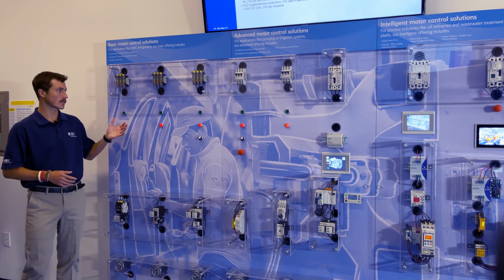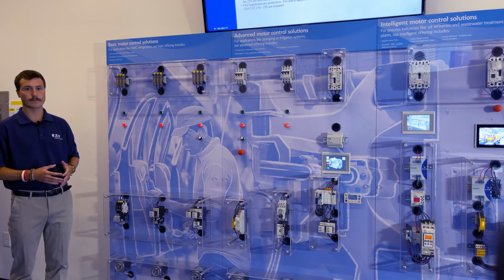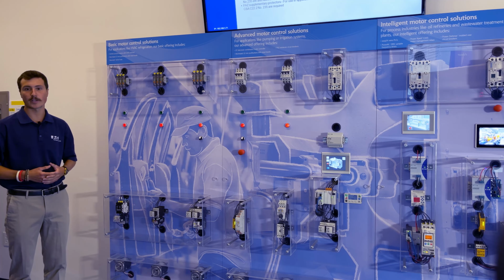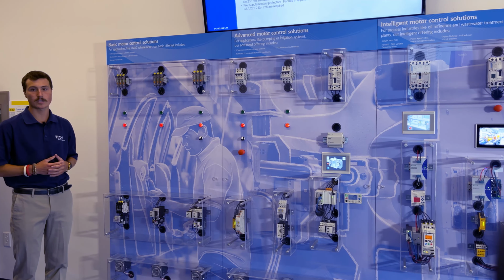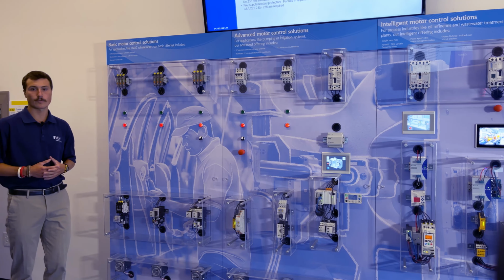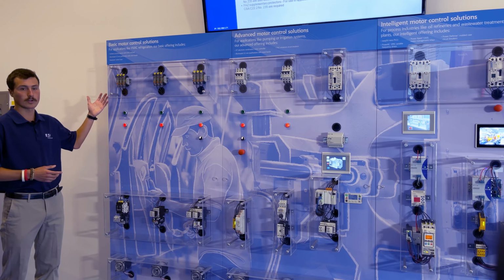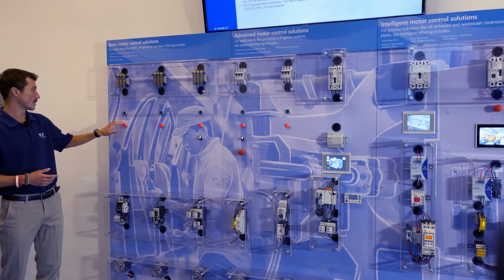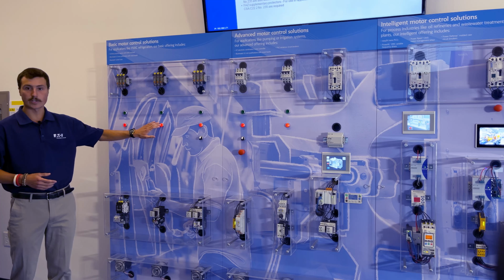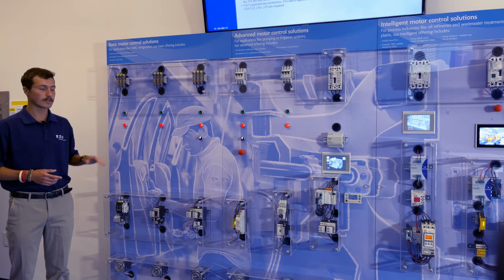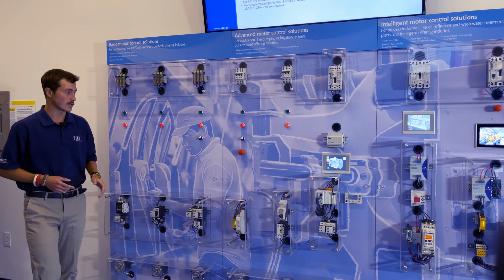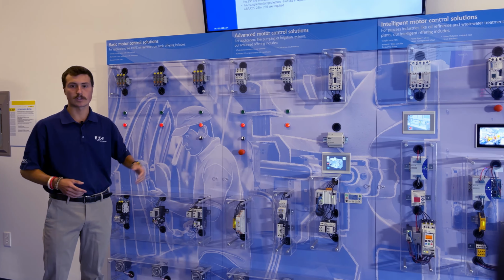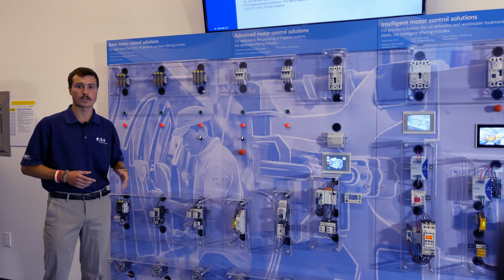Starting with this first configuration, and actually the first three configurations all have in common the Bussmann series fuses for motor protection. We use these fuses because of their versatility and their high short-circuit current ratings. In addition, they also have 22mm illuminated push buttons for start and stop functionality, as well as a selector switch for reversing the direction of the motor on the third configuration.